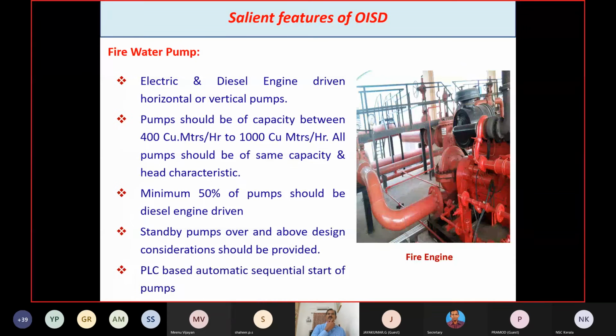And the fire water pumps should be electrical or diesel driven, horizontal or vertical pumps, with capacity between 400 cubic meters per hour and 1000 cubic meters per hour, and all pumps should be of the same capacity and head characteristics. Minimum 50% of the pumps should be diesel driven, because during a power failure the diesel driven pumps can still be operated.